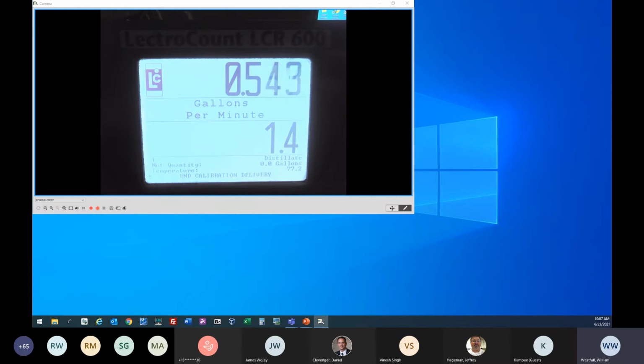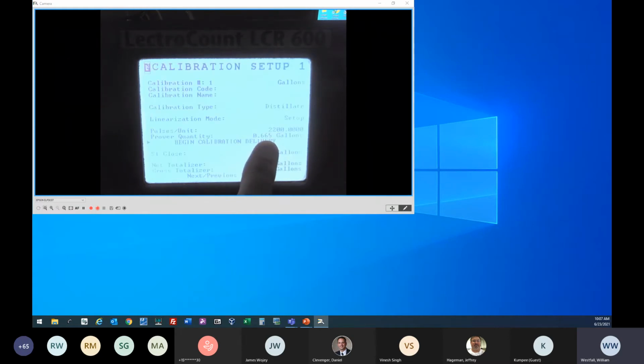So we'll go ahead and end this calibration delivery here. It was set at our prover quantity down here, and this is what was actually on the register. Let's say in this case the prover actually said 0.700, so we were a little bit under. What we would do is arrow up to our prover quantity and hit the enter key. Then we would back up over this. All I'm doing is hitting the up arrow once, because now we get the little over arrow. Then we can enter in 700 using the keypad on the front, and hit your enter key.